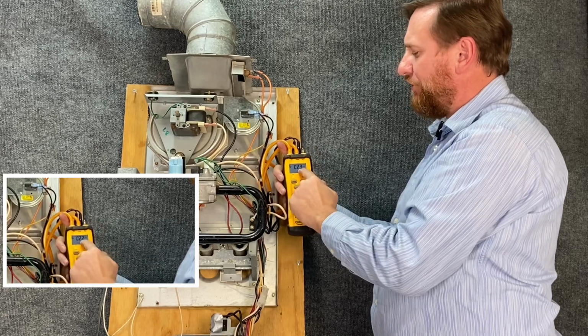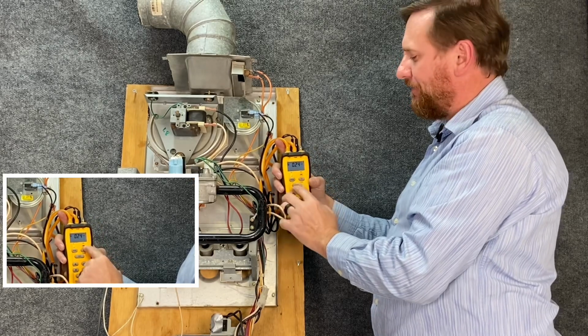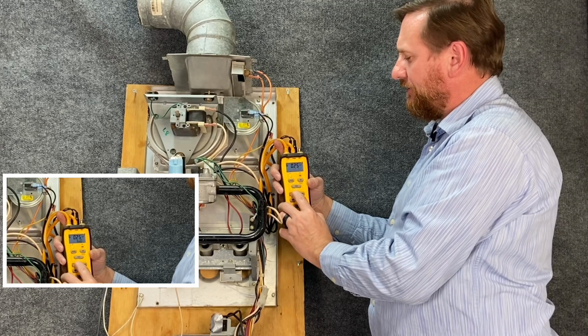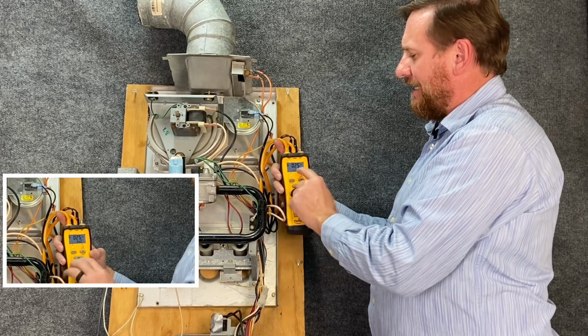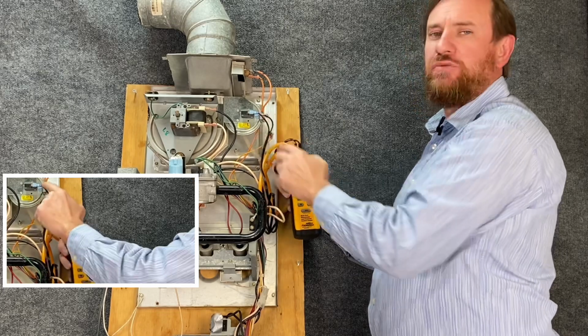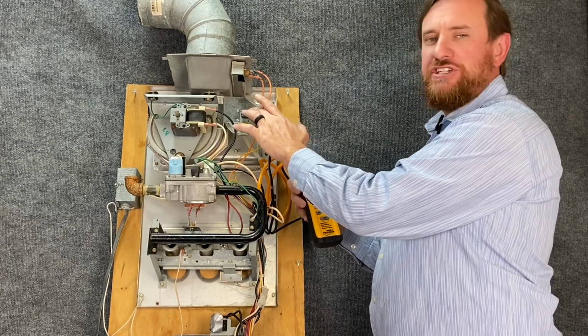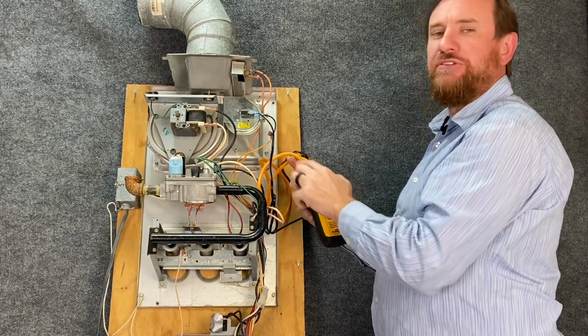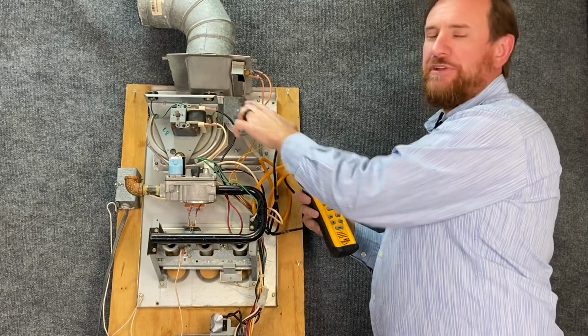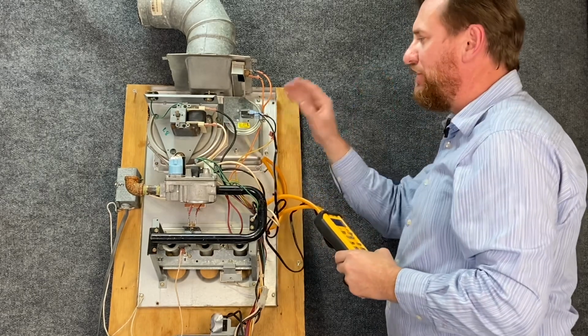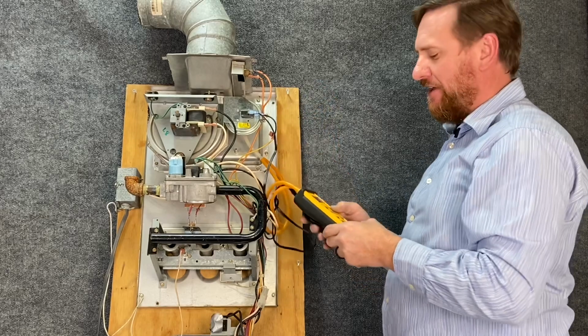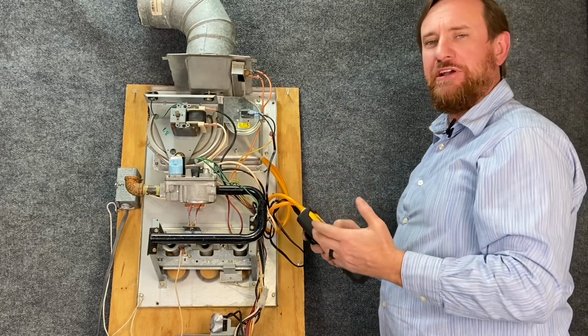So we're at 0.2 and my switch is still open. So we're going to increase it even more. And now we're at 0.25 and my switch closed. So I know that my switch is good. It closed at 0.25 inches of water column, and that's what the switch is designed for. So my switch is working 100% correct. So it's another way of checking the pressure switches.